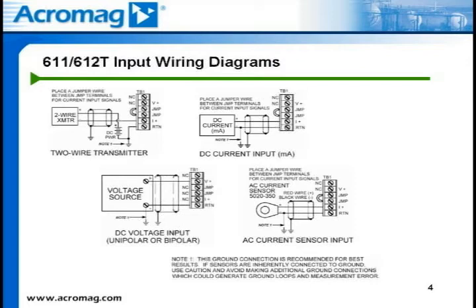Going around the loop and starting with the positive terminal of the two-wire transmitter, wire to the positive side of the DC power supply. From the negative side of the power supply, wire to the RTN terminal of the 611T or 612T transmitter. The negative connection on the two-wire transmitter simply ties in with the I+ terminal on the 611T or 612T module. For current input signals, be sure to place a jumper between the two JMP terminals.